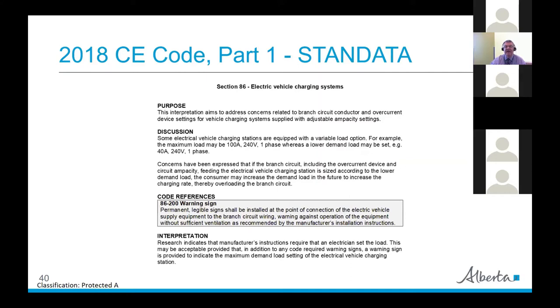We also have a STANDATA on electric vehicle charging systems. We had a situation where the control systems for these charging stations were arriving where you could set the demand load lower than the maximum — for example, the maximum might be 100 amps at 240 volts single phase, and you could set the demand to 40 amps. The interpretation was that manufacturer's instructions require an electrician to set the load, and this is acceptable provided a warning sign is installed to indicate the maximum demand load setting of the EV charging station.